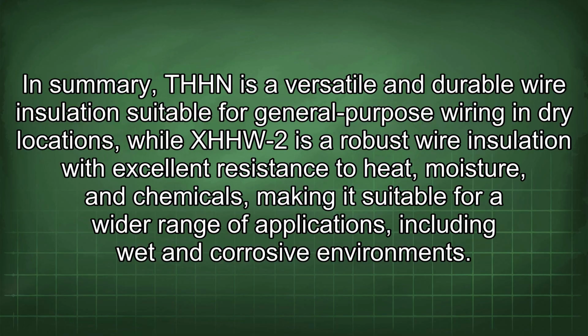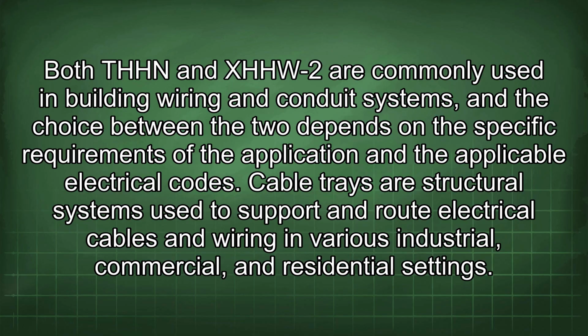XHHW-2 is a robust wire insulation with excellent resistance to heat, moisture, and chemicals, making it suitable for a wider range of applications, including wet and corrosive environments. Both THHN and XHHW-2 are commonly used in building wiring and conduit systems, and the choice between the two depends on the specific requirements of the application and the applicable electrical codes.